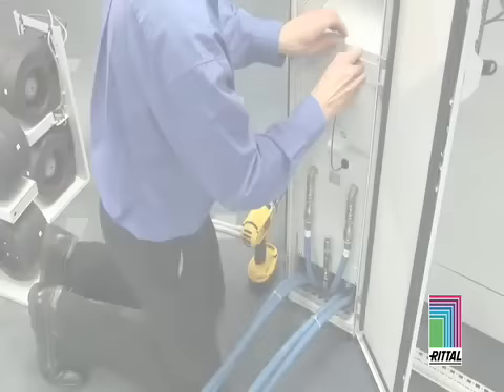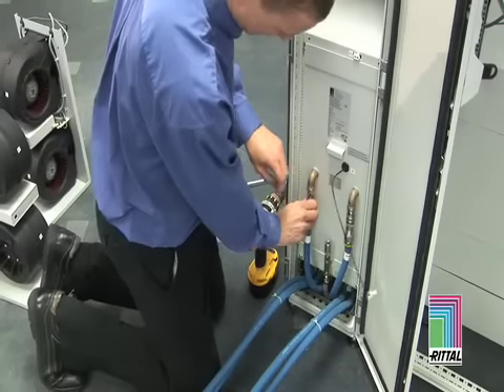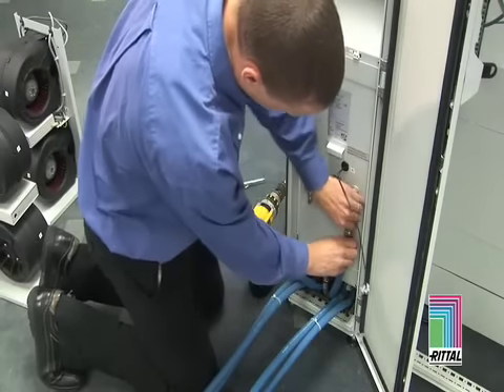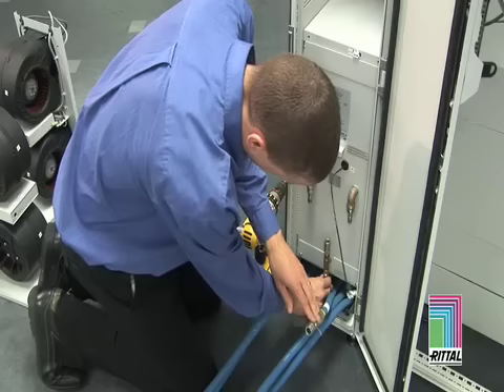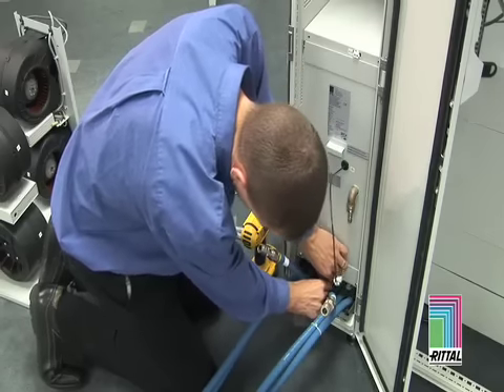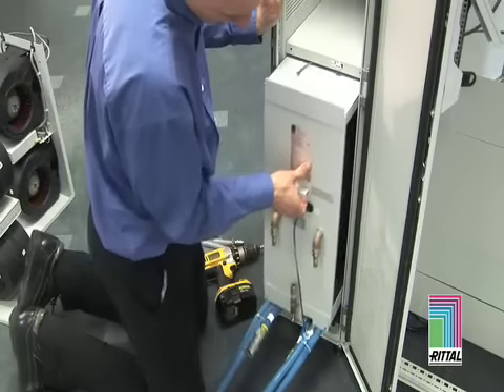Removal of bottom air-to-water heat exchanger. Remove the bottom air-to-water heat exchanger as in the previous steps. Note that you will be required to disconnect the top 2 modules to gain access to the bottom module. Remember to remove the supply side connector first, then the returns.